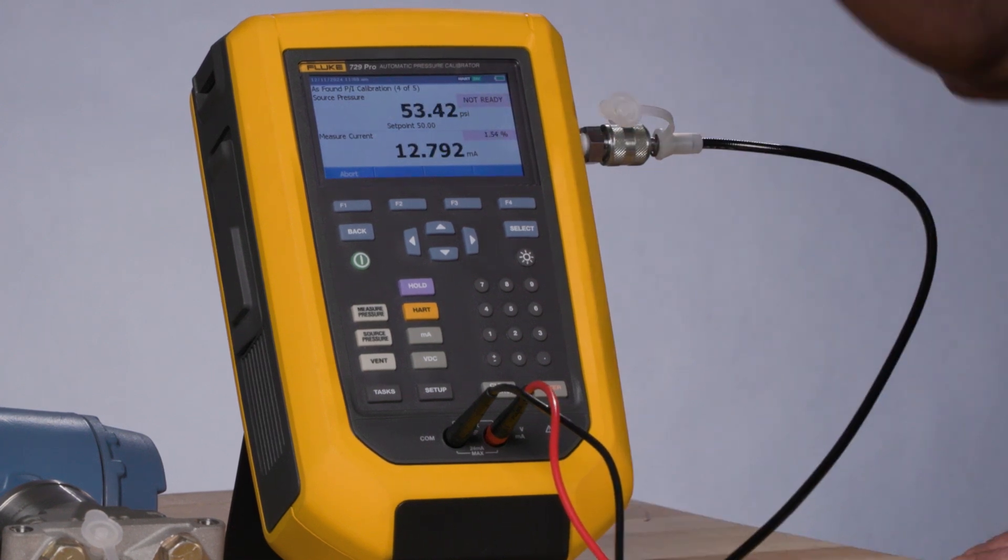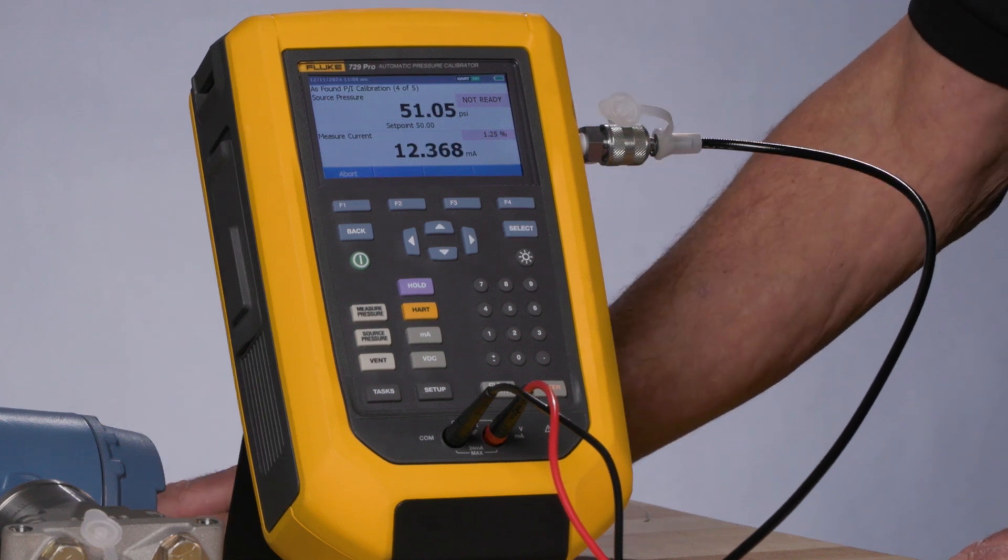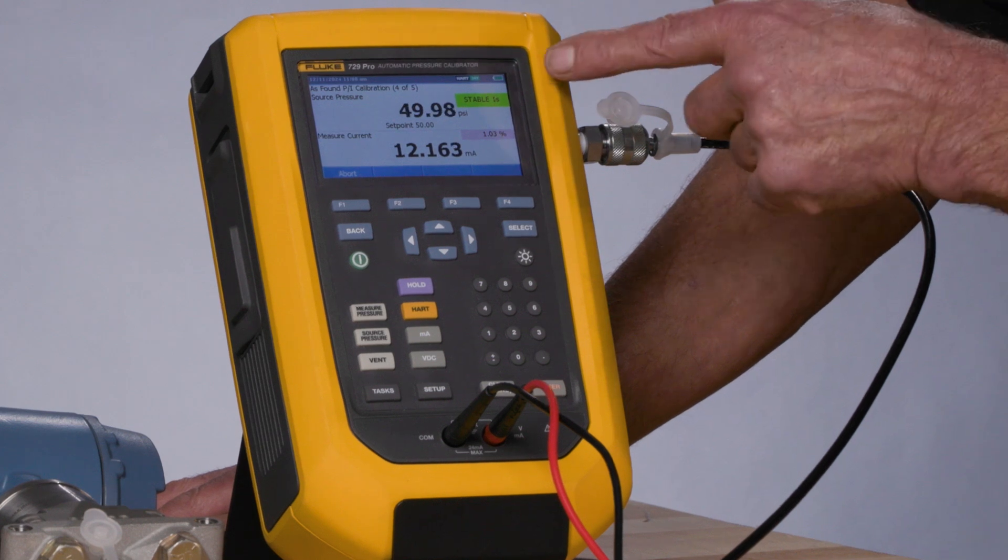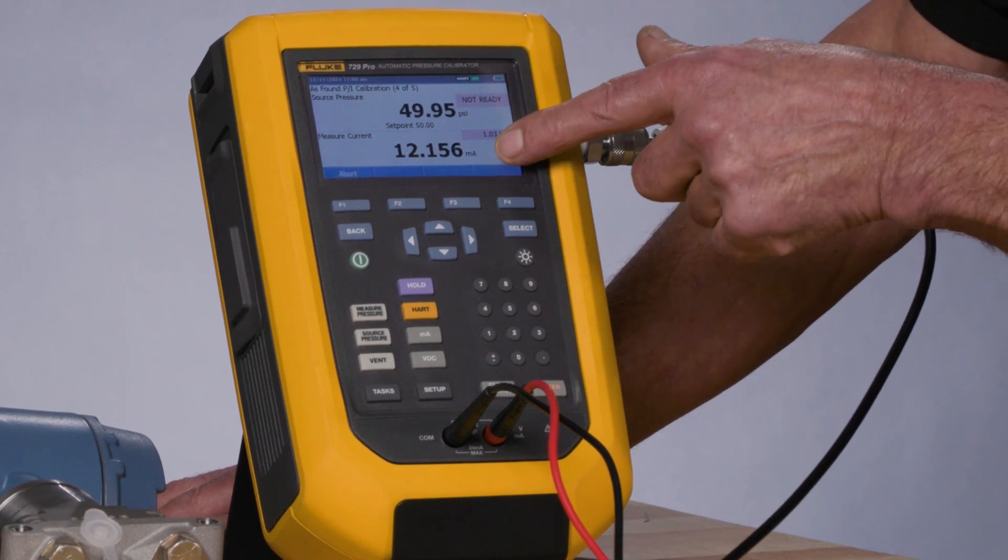Now after 100 psi, it's reducing the pressure to 50 psi, to recheck the 50% point for hysteresis. Stable, error percent, and the milliamp value being recorded.